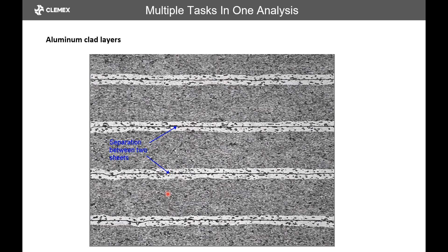This one here is an aluminum sample in which the white lines are clad. Basically, a pure aluminum is deposited or placed over the regular aluminum strip. The idea is that it goes into a radiator, and the clad is there to slow the corrosion. So first we need to identify those middle lines. There's not just one sample, but all of those are separate lines. Again, with those edge finders, we can detect those.